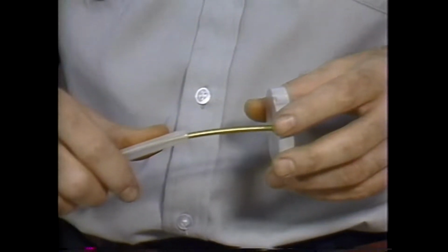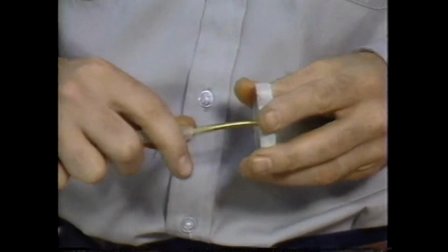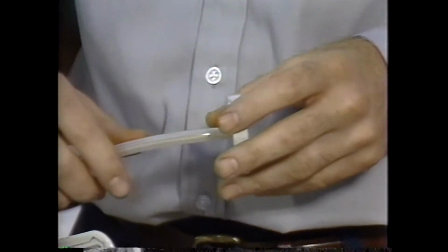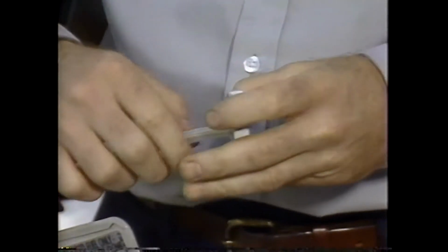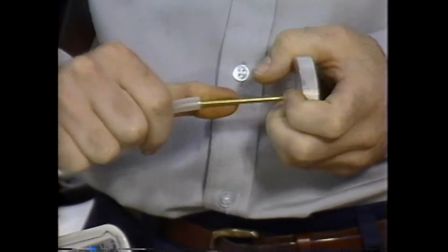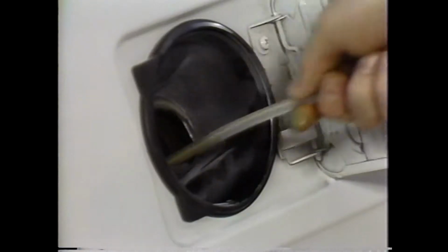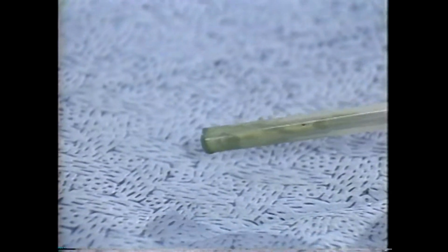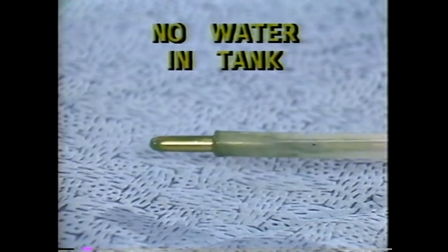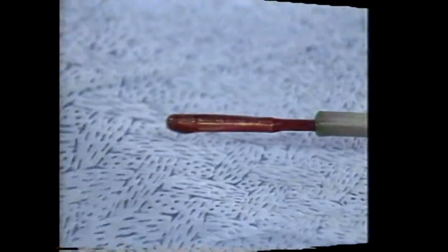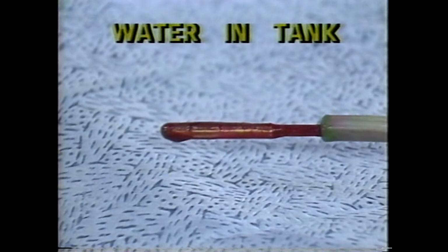Once you've got it inserted all the way, you're going to want to push the cable to once again expose the cable tip out of the Teflon tube. Now wiggle or rotate the whole thing around to make sure that the cable tip gets exposed to the bottom of the tank. Okay, once you're sure you got that done, pull the cable tip back into the Teflon tube to protect it when you pull the whole thing out. If there's no water in the fuel tank, the paste will stay the original color. However, if you do have water in the fuel tank, you might as well stop right here before you do any further tests. You'll have to drain the fuel and clean the fuel tank.